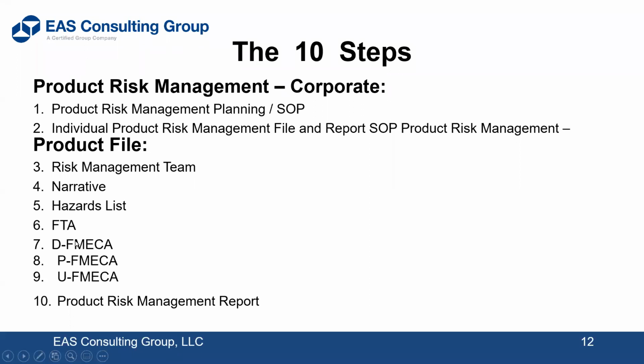A design FMECA, failure mode effects and criticality analysis, a process FMECA, production process, and a use FMECA. And I generally trace all the D, P and U FEMECAs all the way to the user anyway. And I include software in there. I used to have a separate software FMECA, but I just fold software into all of this because basically it's in everything anyway. And then finally your report or your review, which sums up everything, talks about residual risk, and talks about the benefit risk analysis to justify the release of your product to the field, even though there are some residual risks involved.